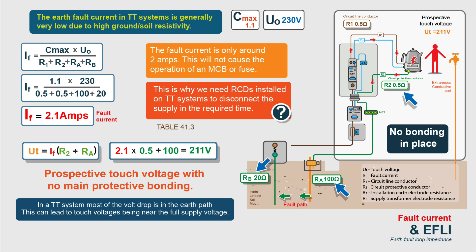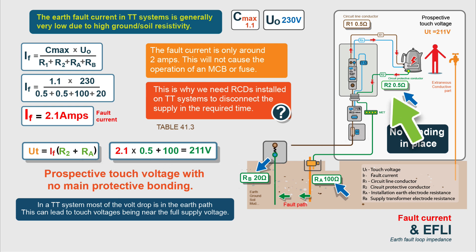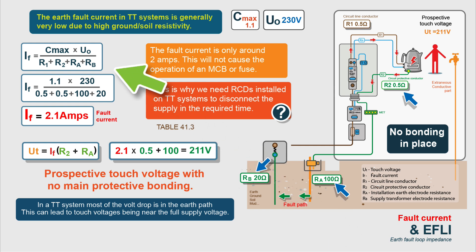This calculation process is explained in another video — I'll put a link to that — but we'll quickly go through it. What we're trying to find out is the touch voltage. The formula for touch voltage is the fault current times R2 and RA. This is the formula for a TT system. Our R2 is the CPC from the fault — in this case it's the kettle — so it's the CPC resistance from the kettle to the main earthing terminal. RA is the resistance of our earth electrode back to the transformer. We get our fault current by multiplying our voltage by Cmax, then dividing by R1 plus R2 plus RA plus RB.